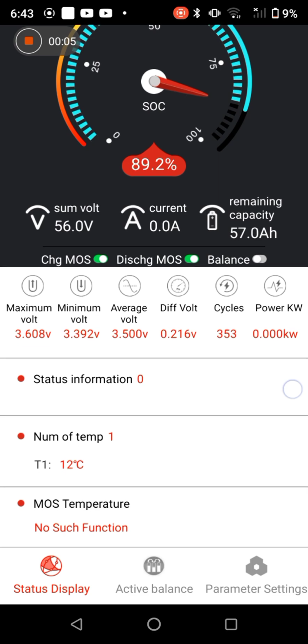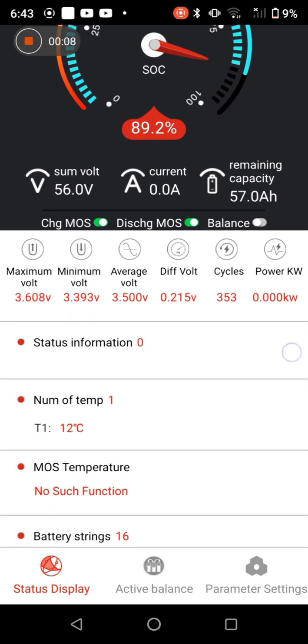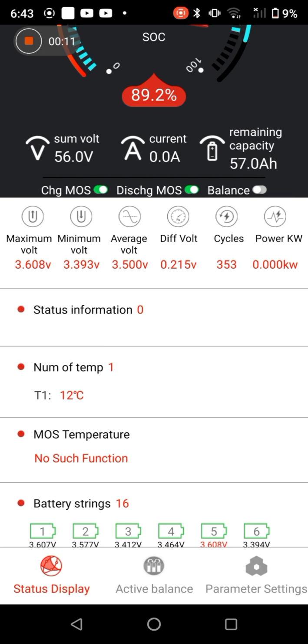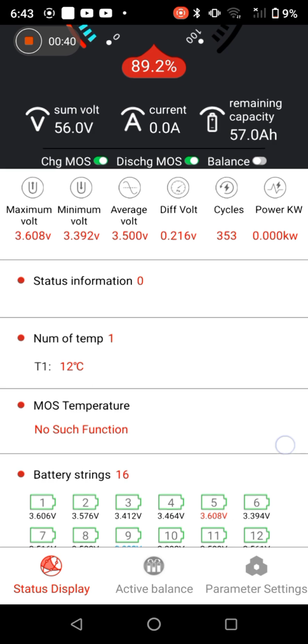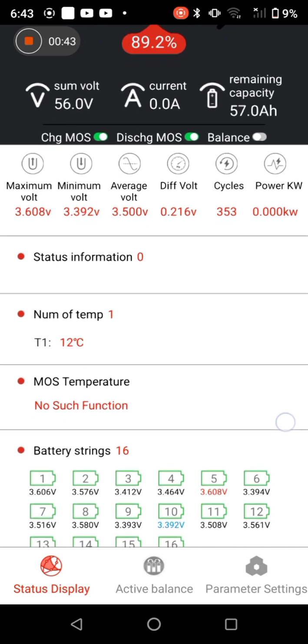Alright, it's still doing its thing, it's been about half an hour. The maximum cell voltage is still up, and the power supply is still up and down from half an amp to an amp, so it's still fluctuating and topping up what the active balancer is shuffling about. So the maximum is still very high and the cell deviation is still high. But what is of interest is the minimum cell voltage, which even in just half an hour has risen to nearly 3.4.